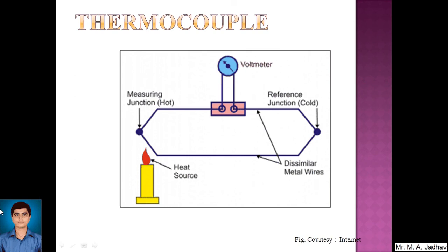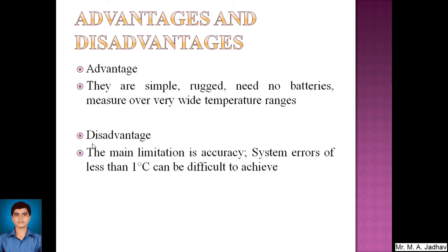Advantages of thermocouples: they are very simple, rugged, and need no batteries because voltage is generated directly by the change in temperature at the junction. They can measure over a very wide temperature range. There are different types of thermocouples — J type, K type, T type — using different metal pairs such as copper-constantan, iron-constantan, and aluminum-chromium. Each thermocouple has its own measurement range.